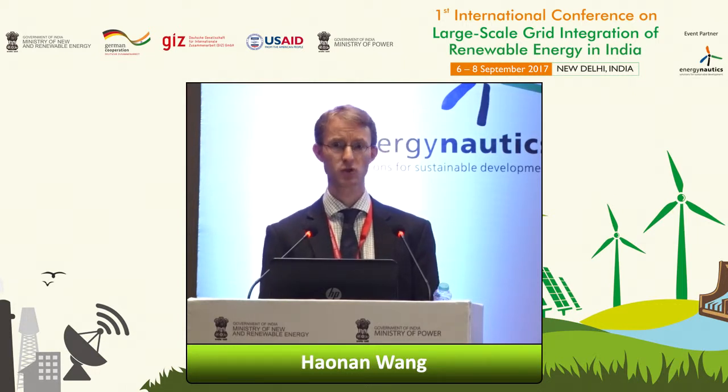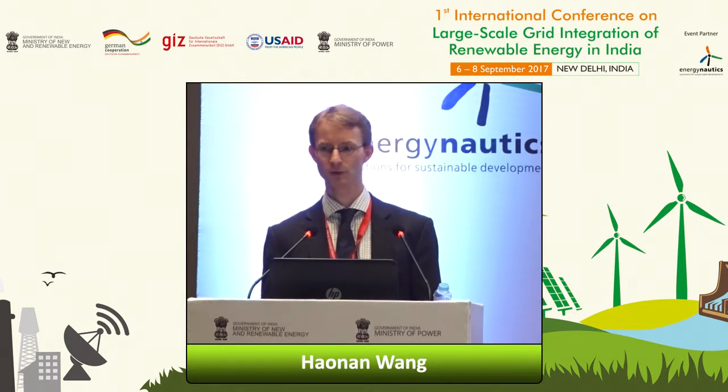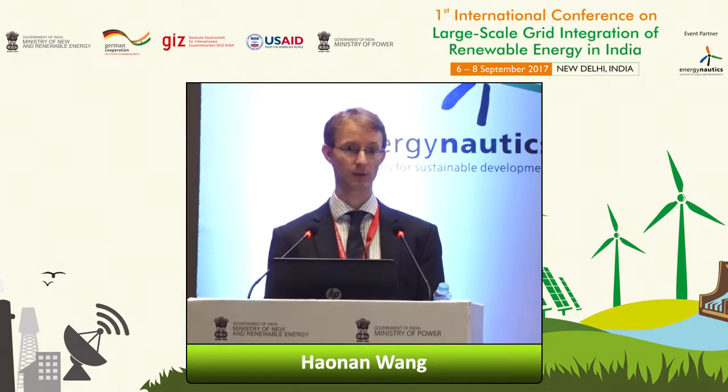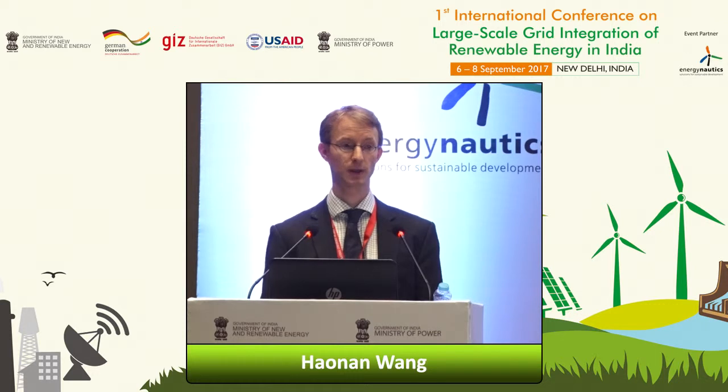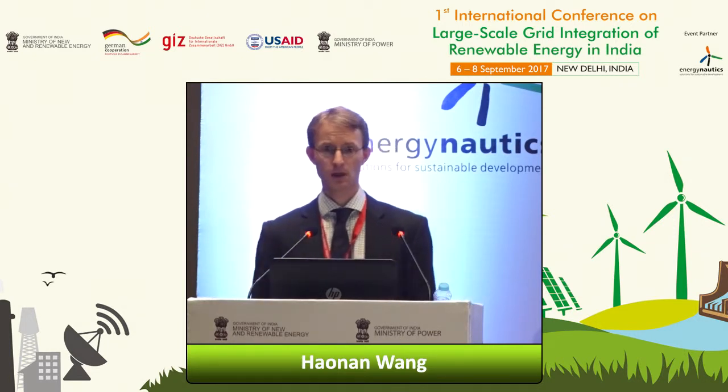So the objective was not to develop a very nice optimal power flow solution, but to have a very pragmatic, simple one. So we don't need any optimal power flow here. We just measure at the grid supply point, and then we distribute the reactive power requirements across all distribution units. This is working quite well in the system due to topology and distribution of plants.